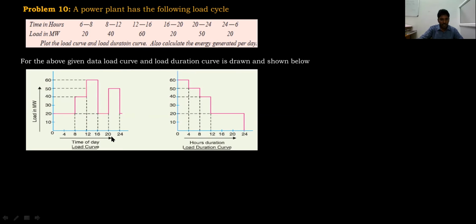This is drawn between 20 to 24, which means 4 hours. So from 4 to 8, the value is 50. In the same way, in descending order, we need to draw the load duration curve, and the area under the curve gives you the total number of units generated in a day.